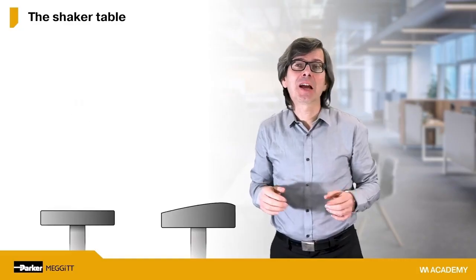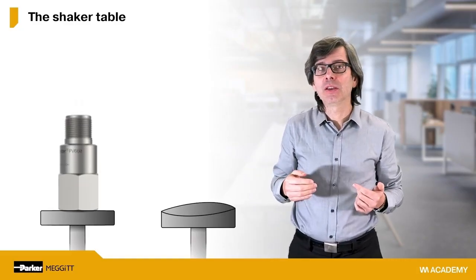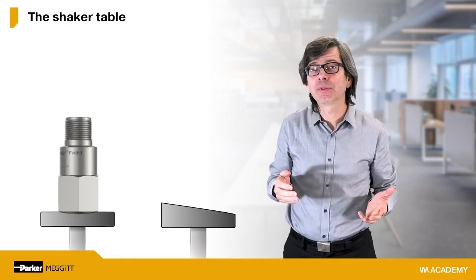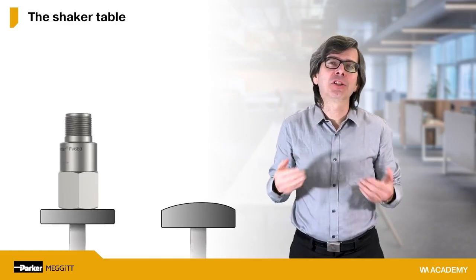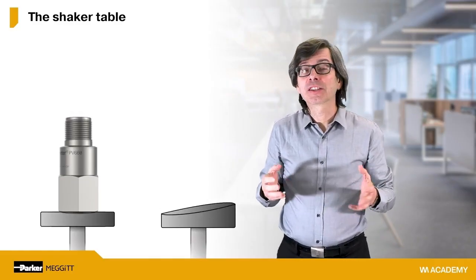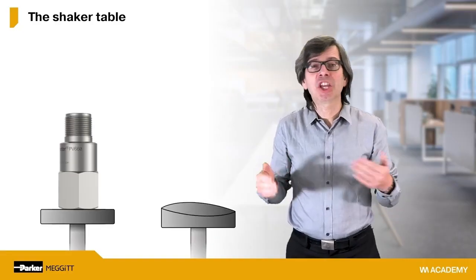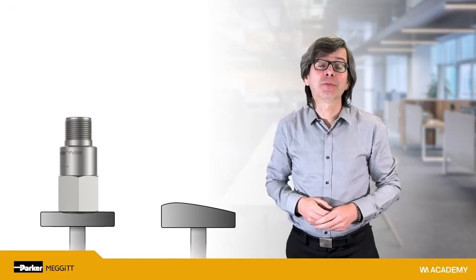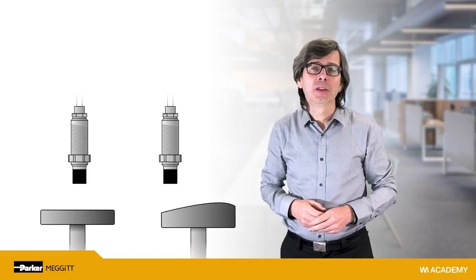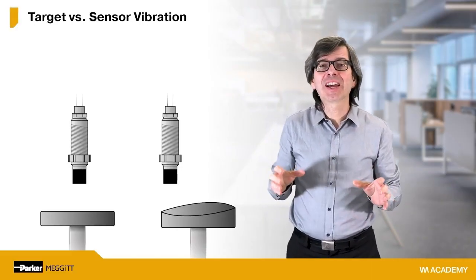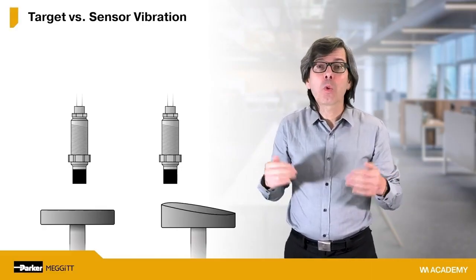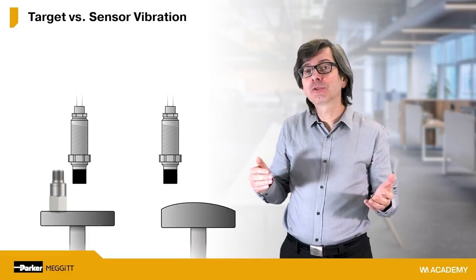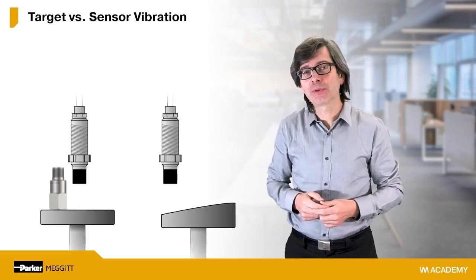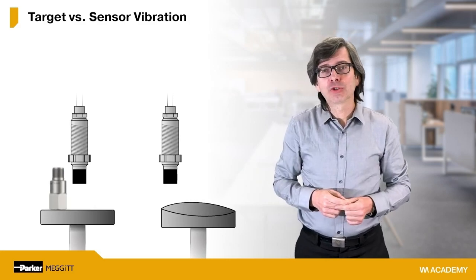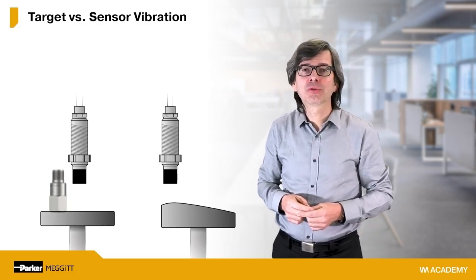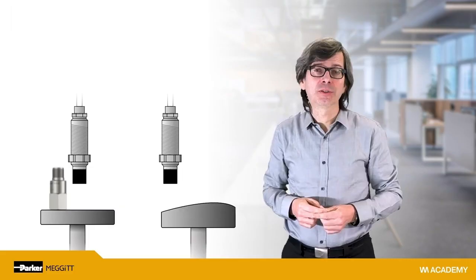Instead of attaching a plate to the vibrating part of the shaker table, sensors such as velocity coils and accelerometers can be attached and then shaken at known amplitudes and frequencies. With a proximity probe, the target vibrates, while with a seismic transducer, the transducer itself vibrates. We will talk more about seismic transducers in the next lesson.